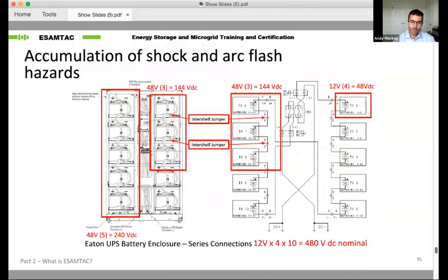Here's another example of the accumulation of hazards. One of the big things for energy storage systems is that they can't be turned off, which is a big difference from typical electrical industry work, where the first rule of thumb is de-energize everything. With energy storage systems, parts of the project simply can't be de-energized. The nuance that's different from PV is that PV is intrinsically current limited, the panels can't output more current than they're operating at. Batteries are entirely different; they can output magnitudes more current than they typically do, and that can become a significant hazard and risk that needs to be mitigated.